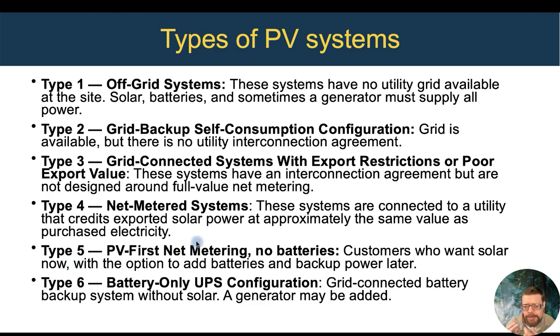Type 5 is we're doing net metering, no batteries. We want solar now, and we're planning on adding batteries later for either backup power or time of use control. And type 6 is the UPS, where we're doing batteries and backup power now, and we might add solar in the future. We can also add a generator to this for additional backup power. Another possible use of this is if we have a certain sort of time of use metering where, for whatever reason, we can't put in solar, or we're going to put it in later, we can use the batteries along with charging from the grid to avoid high time of use charges during a certain period, where it's kind of a UPS but also doing some time of use control.